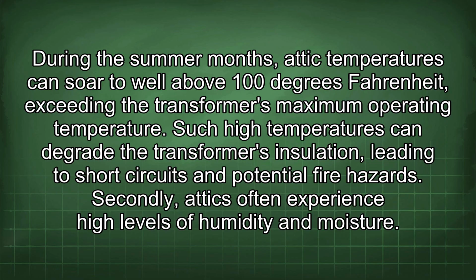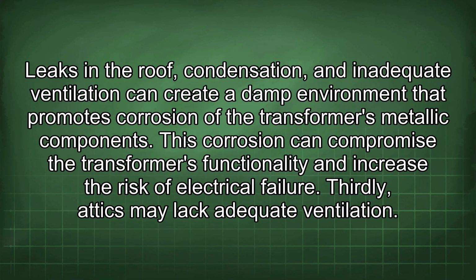Secondly, attics often experience high levels of humidity and moisture. Leaks in the roof, condensation, and inadequate ventilation can create a damp environment that promotes corrosion of the transformer's metallic components. This corrosion can compromise the transformer's functionality and increase the risk of electrical failure.